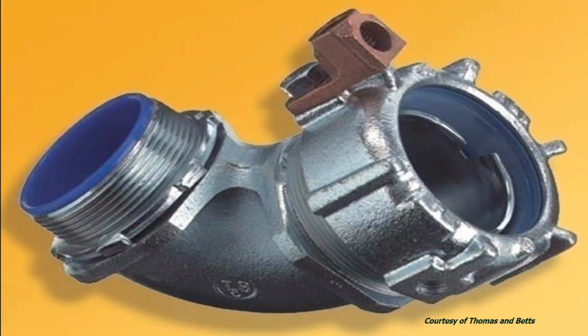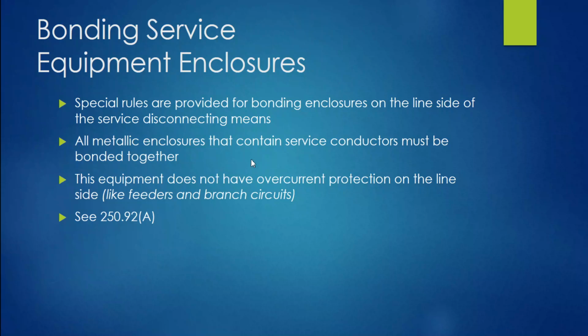All right, this is an example of a fitting that you might use. This is one end where the jumper might go in here, and then you have a fitting that might be just a straight fitting on the other side that'll also have a lug like this, and you actually make the connection, and that would be what you would use to jump over the flexible material that goes in this end. And this is the end that would screw onto the actual enclosure.